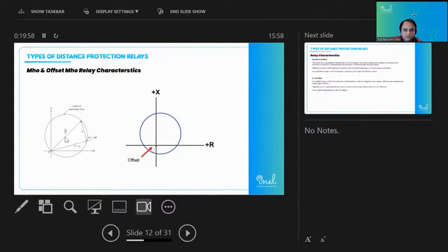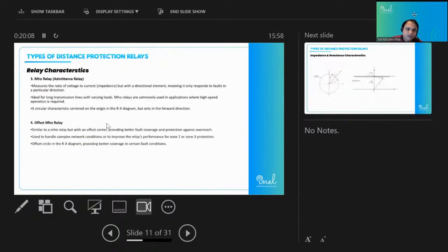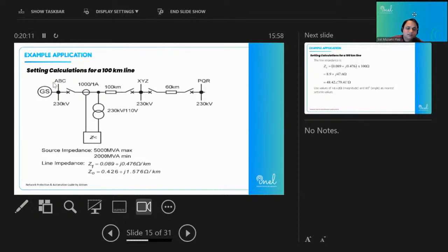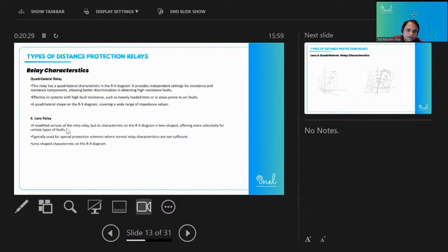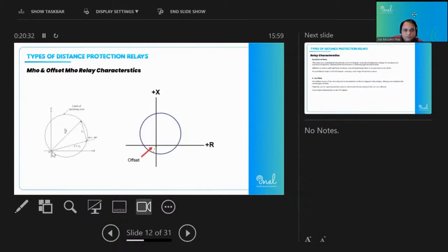It also has some drawbacks, which were later tackled by the offset Mho relay. Like, what happens if there is a transmission line, say this is a transmission line, and our relay is at that ABC location. If a fault occurs at this ABC location, what will happen? Because it is seeing from this ABC to XYZ. But if a fault occurs at this location, this characteristic will be unable to detect it, because it is starting from that exact point where the fault is occurring, and now the relay will be in doubt whether this fault is within the zone or out of the zone.